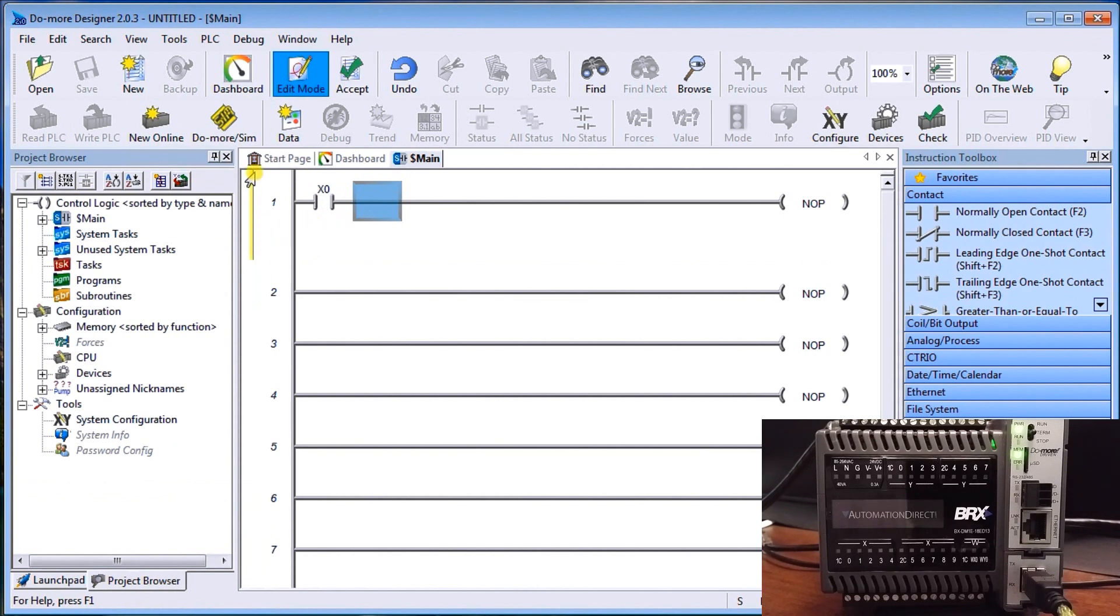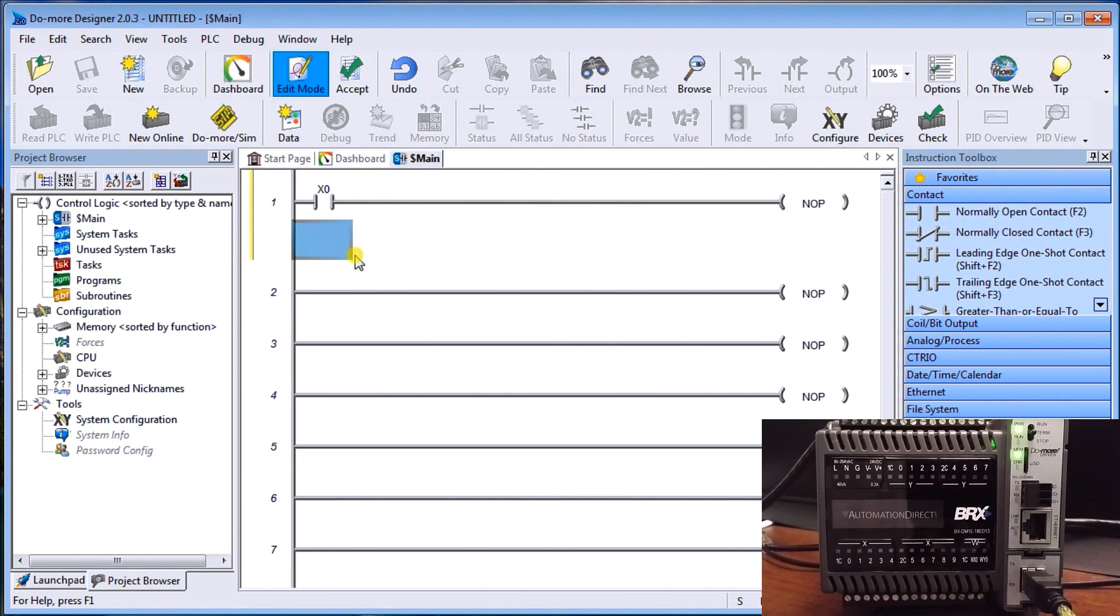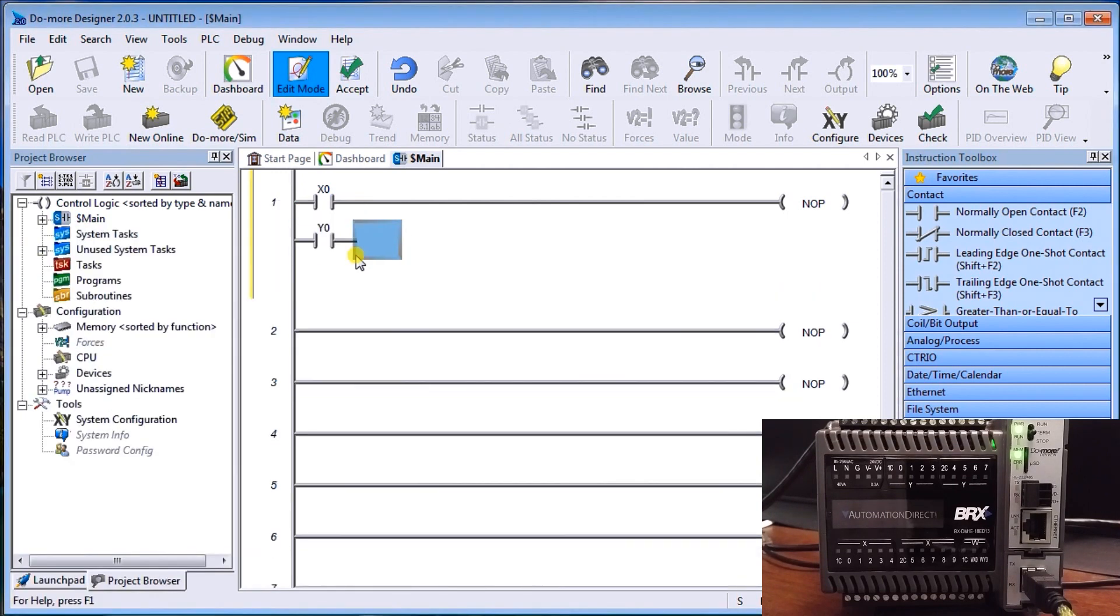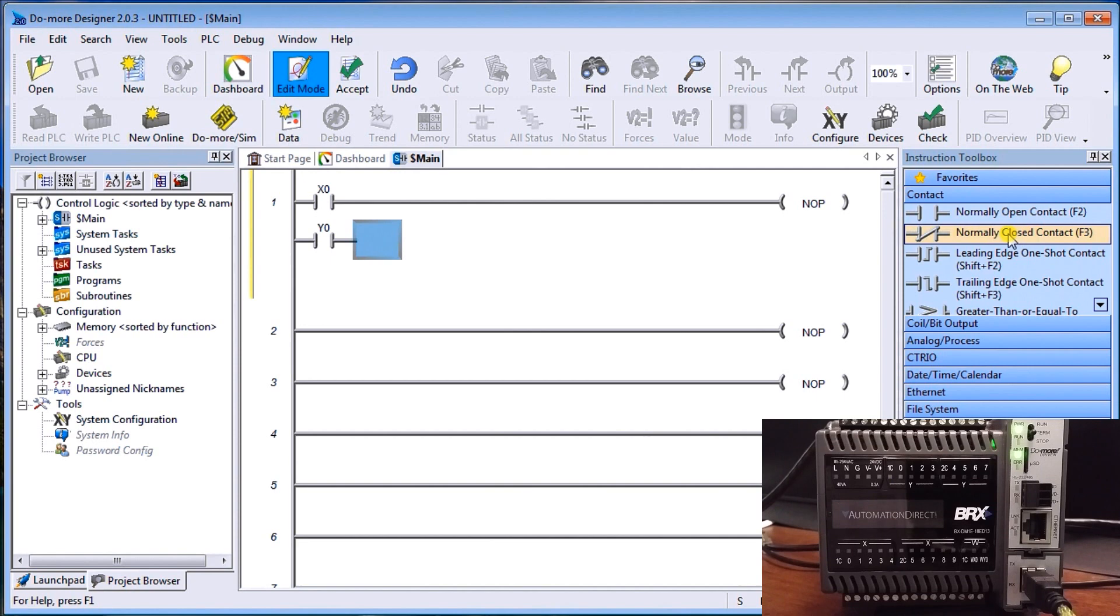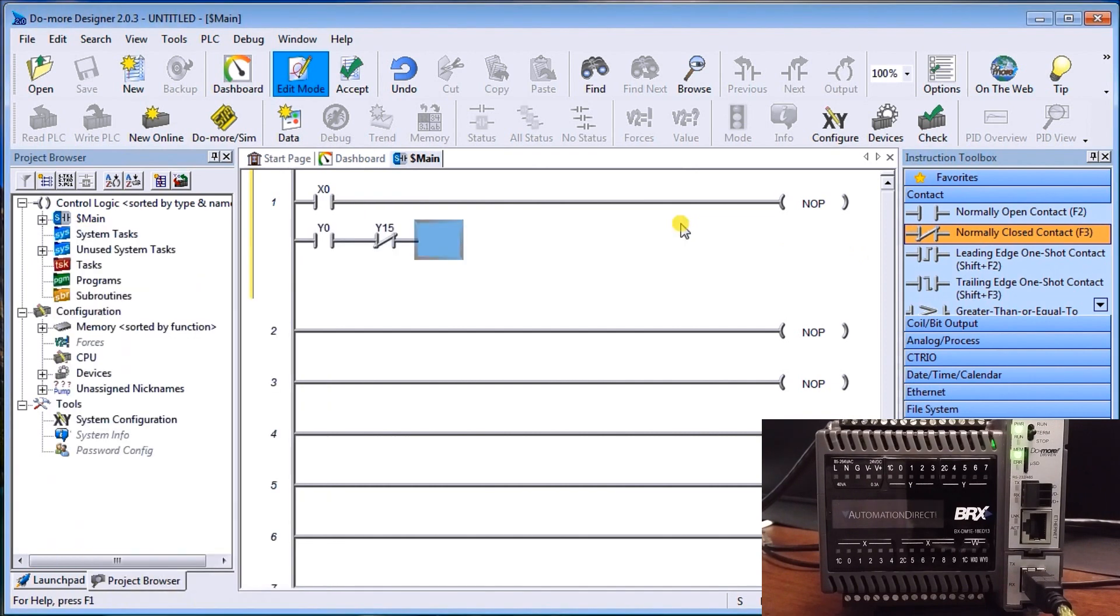You'll notice here that I have this yellow mark. And that yellow mark means I have not accepted the rung yet. So accepted means that it will look at the logic I just put in and determine whether or not it's valid or not. The next part, I'm going to just move my cursor down to the next rung down. We're going to put another contact here. It's going to be y zero. And hit enter. And we're going to have it normally closed, which is now going to be F3. We can also double click it over here and it will put it up for us. And hit enter.